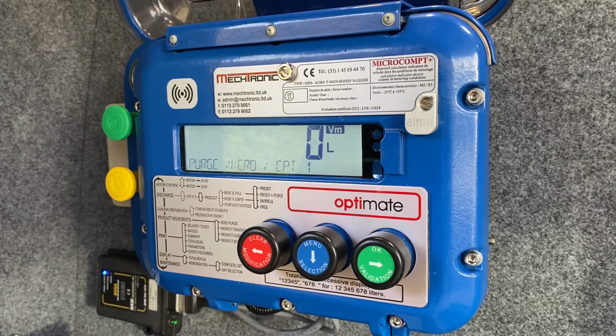What OptiMate will do now is empty the manifold of gas oil first. Once the manifold is empty of the 10 litres, it will then open the kerosene compartment number 1. Once the manifold is full of kerosene, it will push 90 litres through the delivery system, reaching a 100 litre delivery, ensuring no contamination occurred through this process.